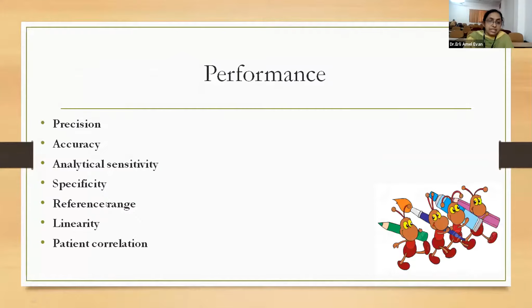Performance can be assessed by precision, accuracy, analytical sensitivity, specificity, reference range, linearity, and patient correlation. For CSF, particularly, we have to look at the LOB. If it is more, you have to report the LOB, the limit of blank, and cleaning cycles have to be given for the machine. If there is a flag sign for any parameter, it indicates spurious results, such as platelet counts, where cell debris will be there.